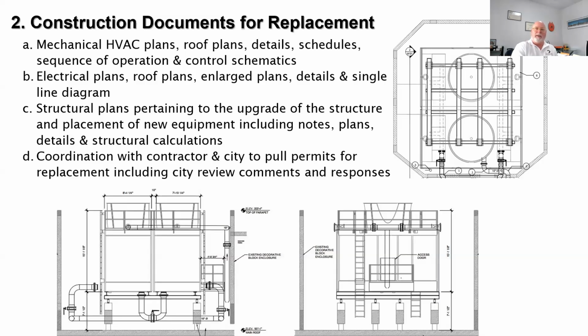Construction documents detail the plans, schedules, and details, including how we want the tower to operate. This is also a time where we can make changes, especially here in South Florida, where during temperate periods we may not want the tower to cool the water because the building needs to maintain some heat. The old design required going through the tower, but we might put in a bypass and change the sequence of operation so that during those times we can bypass the tower and maintain heat in the building.